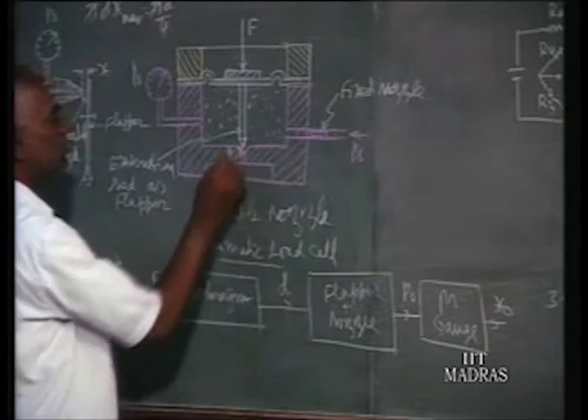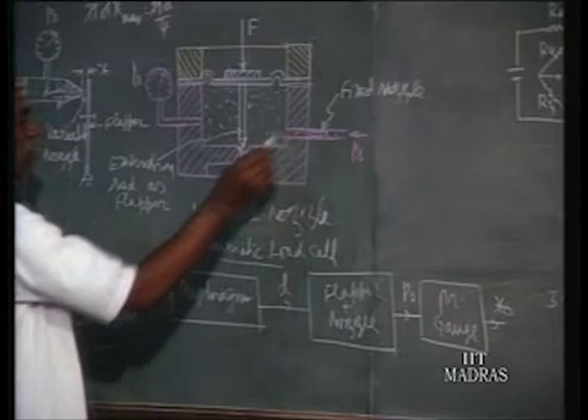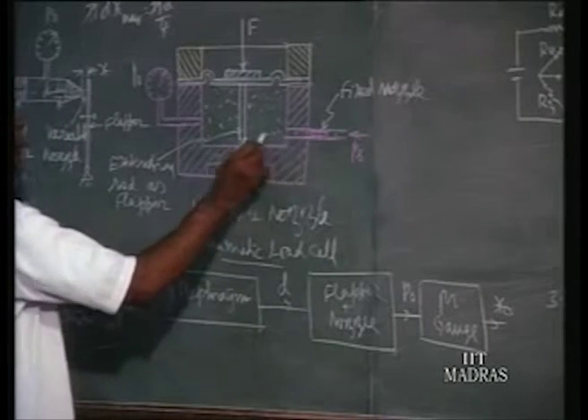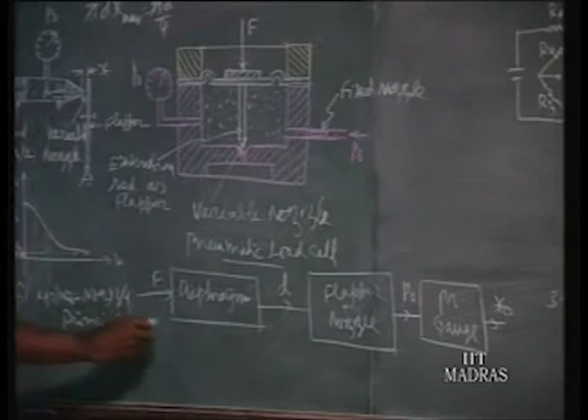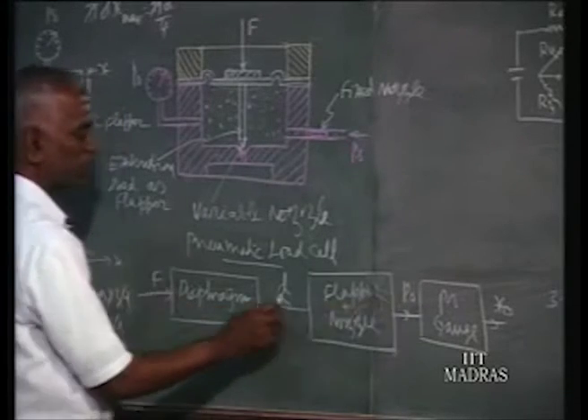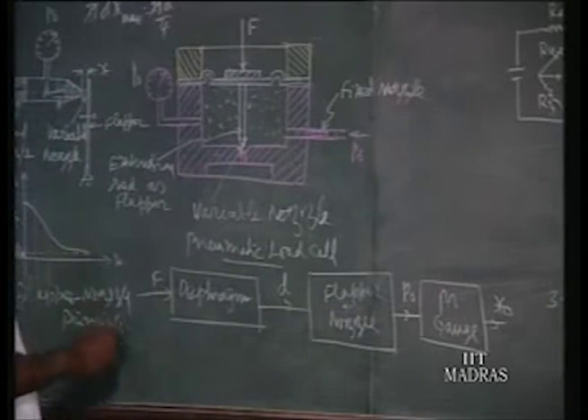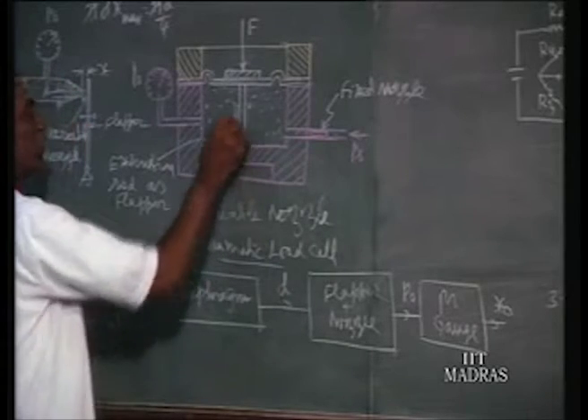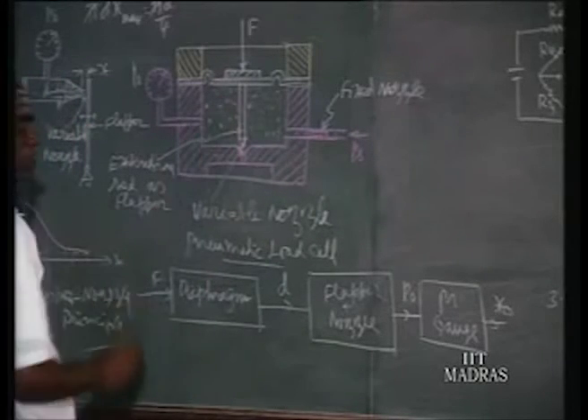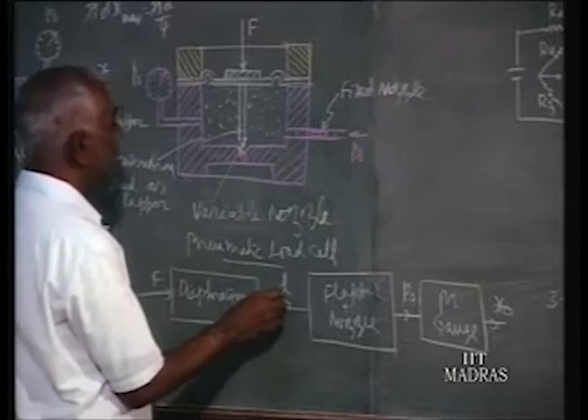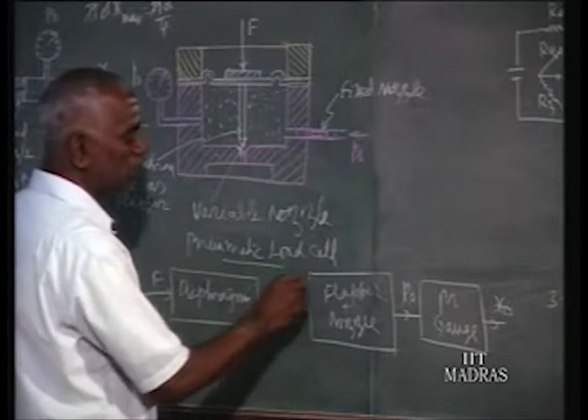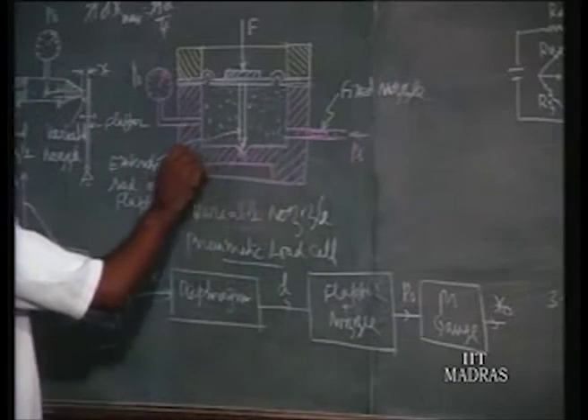So this distance is converted, because this is a fixed nozzle, this is a variable nozzle. In between these two nozzles, we call it the chamber here. So the chamber pressure is a function of the amount of opening here. The amount of opening is nothing but our displacement in the extension rod, so that is proportional to that extension rod. So D is converted into PO by this flapper nozzle system.